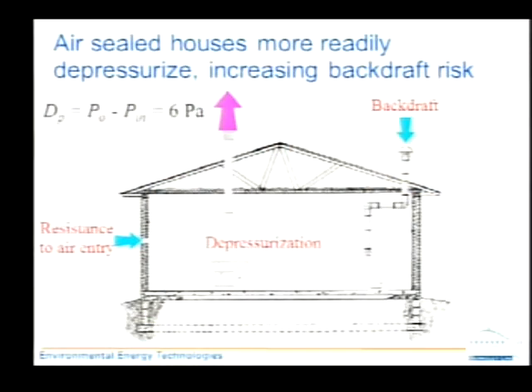Now, the furnace is probably an example, because it's very uncommon to still have natural draft central furnaces. But if you're looking at a wall furnace, most wall furnaces are still natural draft. So a natural draft wall furnace, you could pull exhaust back in, or a water heater. So that's this issue. We actually think the concern about it is somewhat overstated. We think people are getting scared about a lot of homes and situations that they probably shouldn't be scared about, especially in contrast to the fact that they're not concerned at all about their cooking burners, which are backdrafting all the time. But this is the issue, and obviously we don't want this to happen. This is not the way these things are designed to work. So when we start putting in kitchen exhaust, we need to pay attention to this.